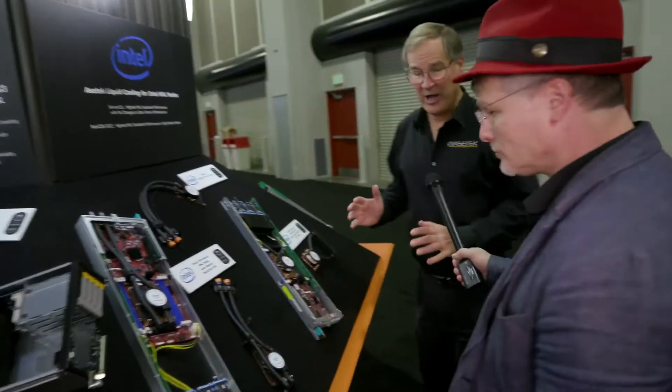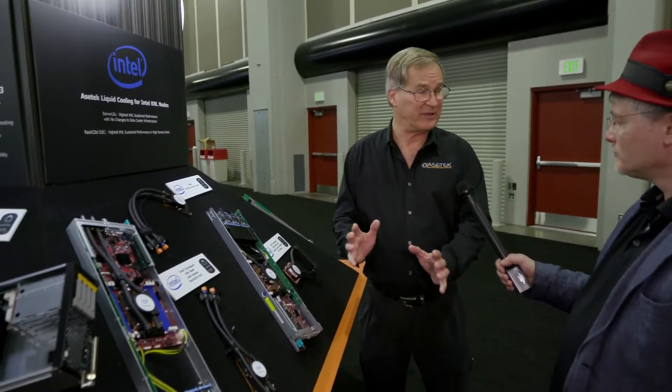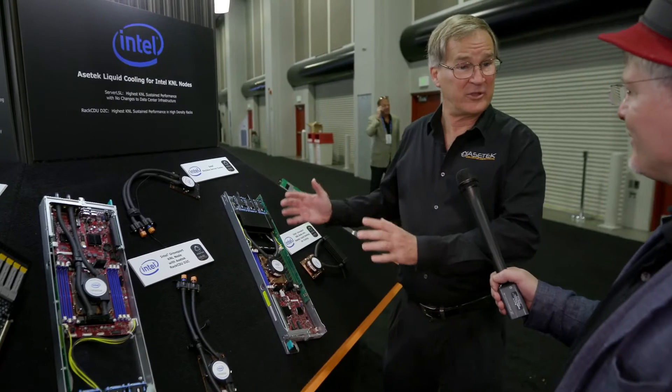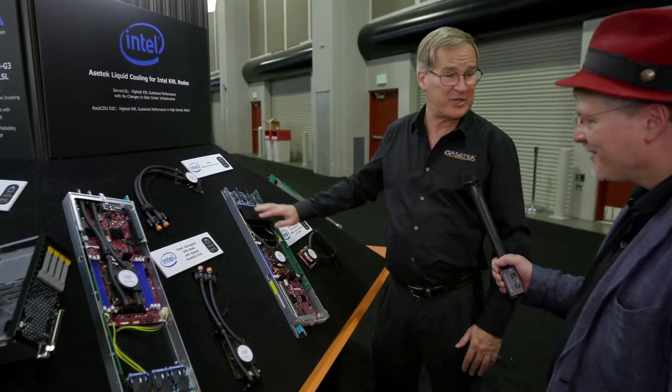In the past, we've predominantly talked about our direct-to-chip RackCDU system, which is a data center level liquid cooling system. It gets all of the heat into liquid and takes that out of the data center in an all-liquid path where it can be disposed of for free, or it can actually be recycled in a waste heat recovery scenario. One of the things we're seeing is that as Intel, NVIDIA, and others bring out higher-power systems, there are a lot of all-air-cooled data centers that want to take advantage of those processors. So we've brought to market something we've been doing in the desktop arena for many years.